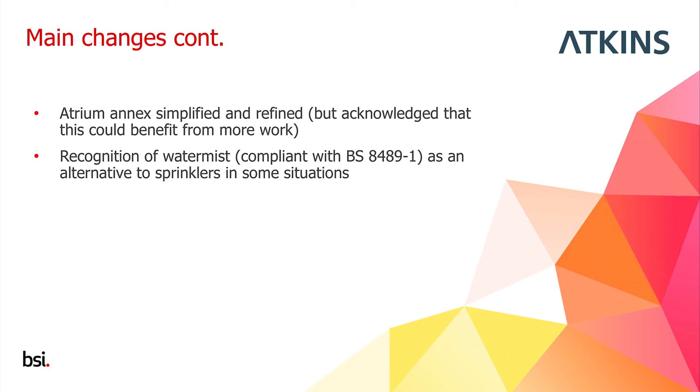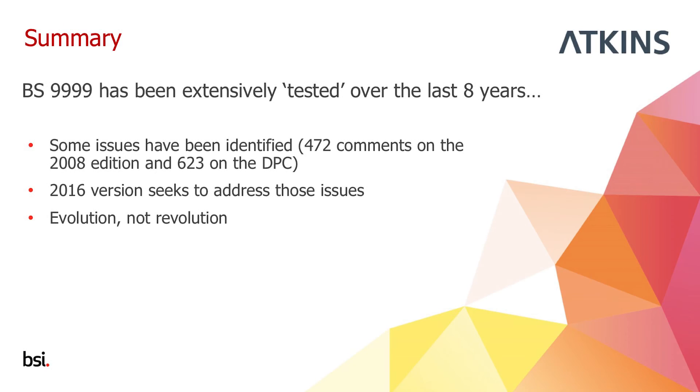Water mist has now been recognised as an alternative to sprinklers in BS9999. Fitting sprinklers in a building gives certain design freedoms by altering the risk profile. In the 2008 version it was suggested that other suppression technologies might give equivalent benefit but required proof. Now that British Standards exist describing what a good water mist system looks like for both domestic and non-domestic premises, the standard states that in certain respects a water mist system provides the same benefit as sprinklers.